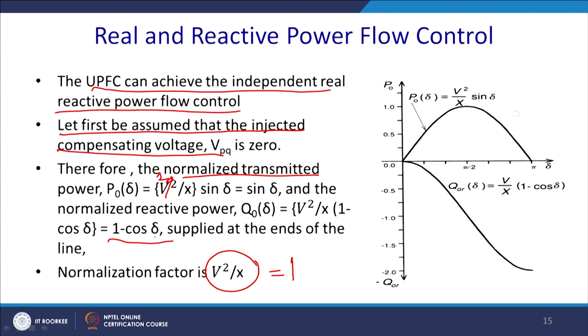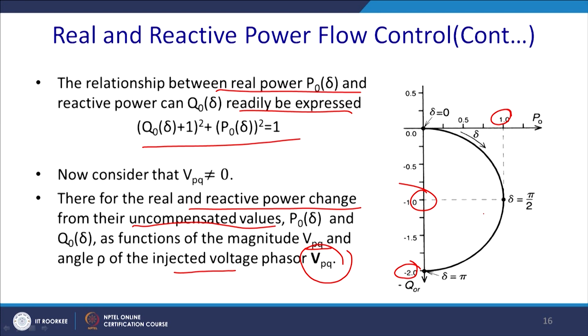Now, the relationship between the real power P delta and the reactive power Q delta can be expressed basically in a unit circle form: Q delta plus 1, the whole squared, plus P delta square equal to 1. Thus, you have a center at this point. Now, consider that VPQ is not equal to 0; then you are injecting some voltage, and therefore the real and reactive power exchange from the uncompensated values of P delta and Q delta is a function of the magnitude of VPQ and the angle rho of the injected phasor. Thus, this circle will shift.